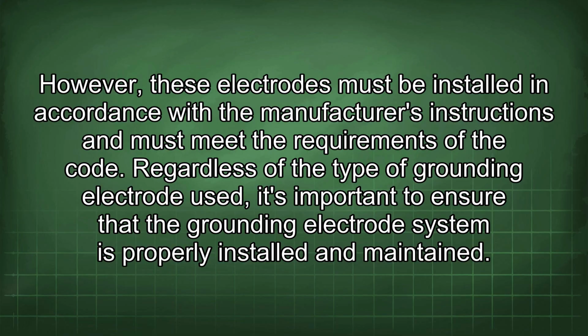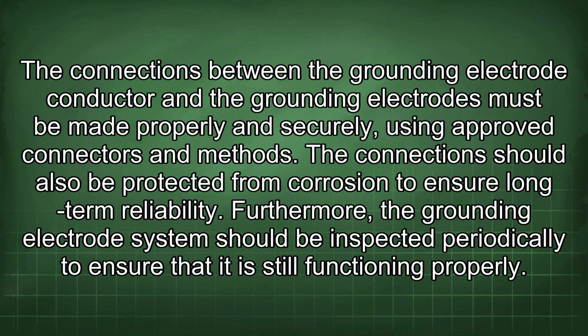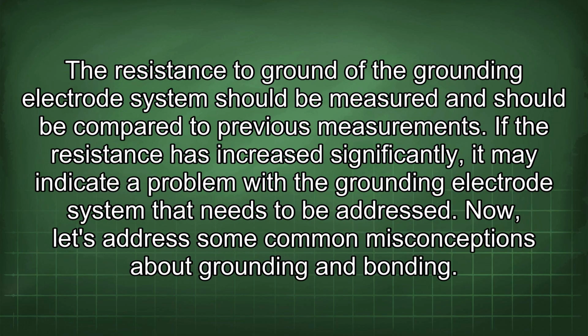Regardless of the type of grounding electrode used, it's important to ensure that the grounding electrode system is properly installed and maintained. The connections between the grounding electrode conductor and the grounding electrodes must be made properly and securely, using approved connectors and methods. The connections should also be protected from corrosion to ensure long-term reliability. Furthermore, the grounding electrode system should be inspected periodically to ensure that it is still functioning properly. The resistance to ground of the grounding electrode system should be measured and should be compared to previous measurements. If the resistance has increased significantly, it may indicate a problem with the grounding electrode system that needs to be addressed.